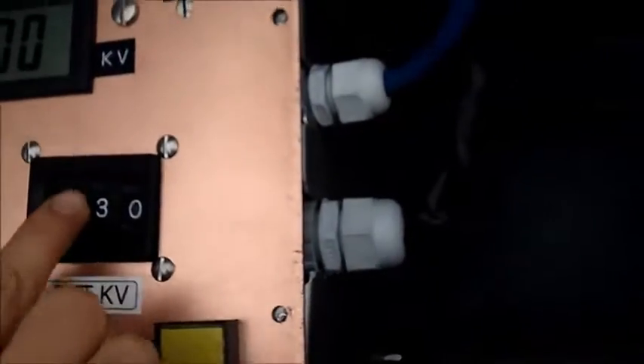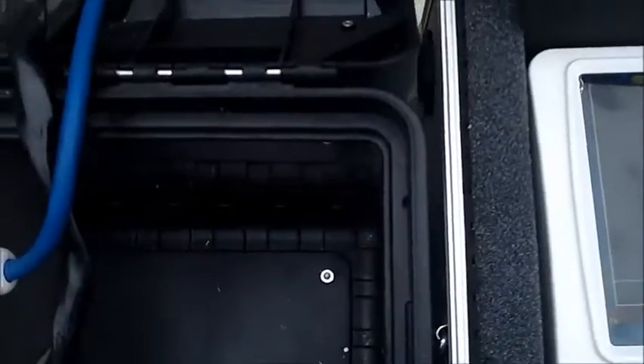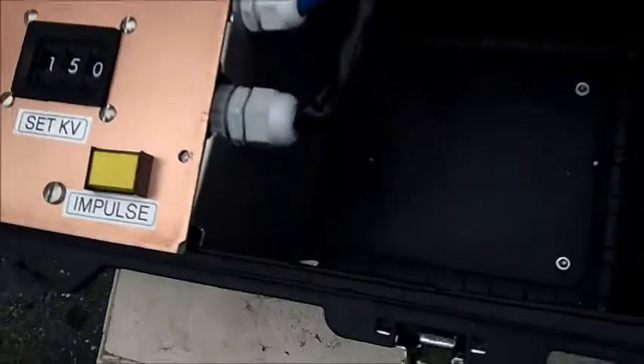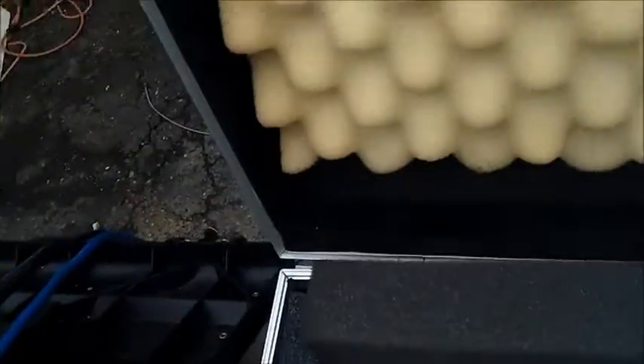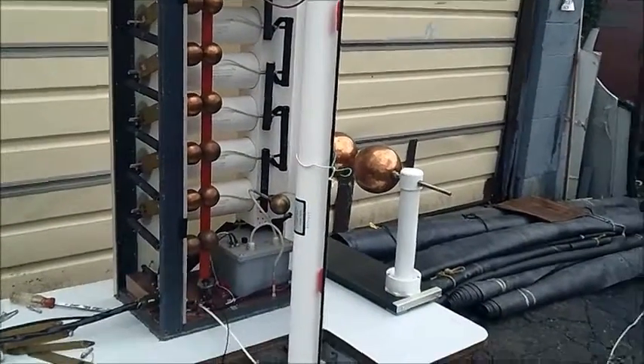We're going to raise the voltage to 150 kV. Turn high voltage on. Reset the scope to make a single shot — it charges up. At 150 kV, press the impulse and see the waveform. The reading is a bit high so we're going to calibrate the system with a sphere gap.